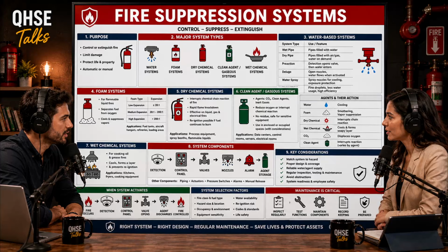Why build a system that requires 2 totally independent triggers? Why make it so complicated? It's all about preventing accidental water discharge in highly sensitive environments. Imagine a multi-million-dollar data center housing critical servers, or a museum vault with priceless artifacts. Right, environments where water damage is just as catastrophic as fire damage. Exactly. Let's say you have a basic wet pipe system in that data center. A maintenance worker on a ladder accidentally swings a wrench and knocks the glass bulb off a sprinkler head. Oh no. Hundreds of gallons of black water blast all over the servers. Total loss.